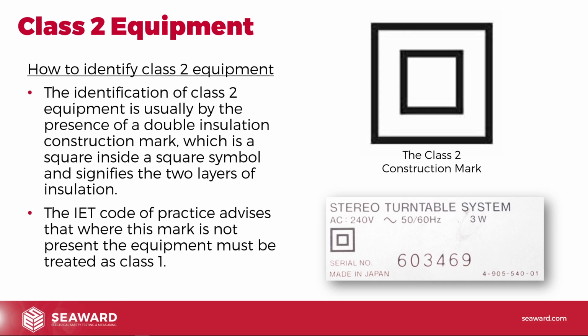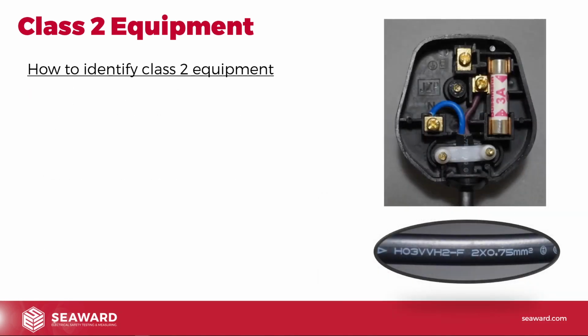Now the class 2 construction mark should be on all class 2 equipment, so generally that's the definitive guide. If you don't see the mark, it's not class 2. If you see the mark, it's class 2. So generally that's the easy way of doing it. Now sometimes the mark might have got scratched off, it might not be apparent, so you might need to do a bit more investigation. So what do we do in that case?